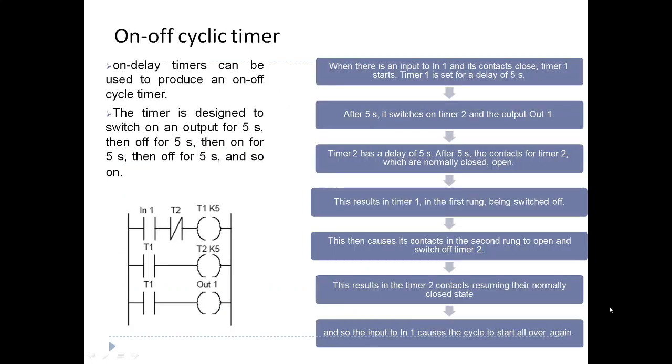On-off cyclic timer. When there is an input 1 and the contacts close, the delay for 5 seconds is set. On-delay timers can be used to produce an on-off cycle timer. The timer is designed to switch an output for 5 seconds, then off for 5 seconds, then on for 5 seconds, and off for 5 seconds, and so on. This is a cyclic timer.